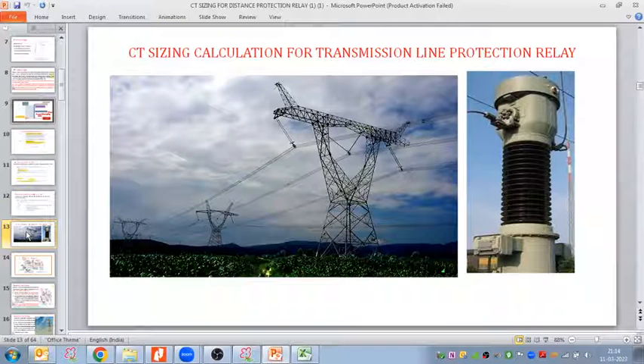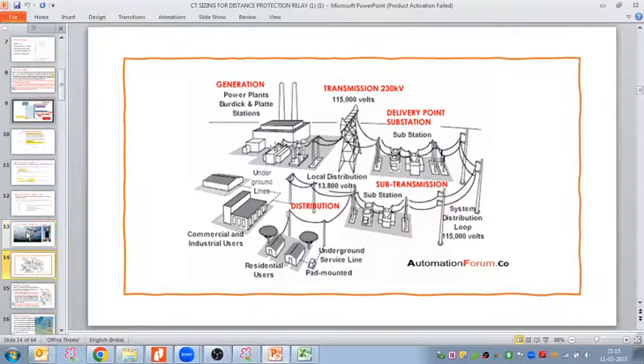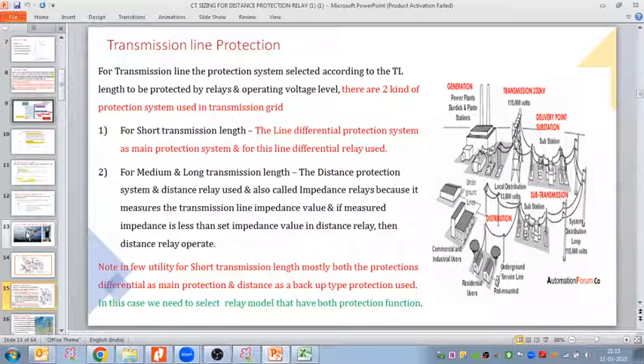So we are entering into the CT sizing calculations for transmission line protection relays. For the transmission protection relay, we discuss what kind of protection relay we use. Briefly, this all we will discuss in the protection module; just for the relay selection we are discussing this point. Based on the transmission line length and the transmission line operating voltage, we need to select the relay for the transmission line.